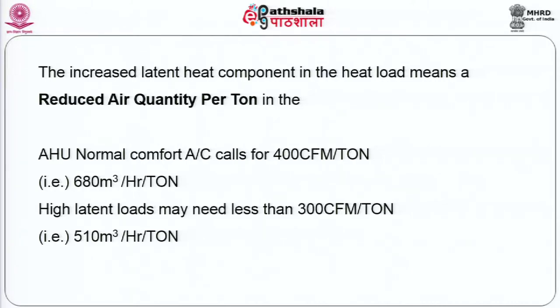In an auditorium, it increases to 10 square feet a person, which means the human load inside increases to something like a minimum of 10 times. With this increase in latent load, basically the air quantity comes down. You can see that in comfort air conditioning, the air quantity per ton would be roughly about 680 meter cube per hour per ton. Whereas in high latent heat loads, like let us say an auditorium, one can go down to 300 and even lower figures for bigger auditoriums.